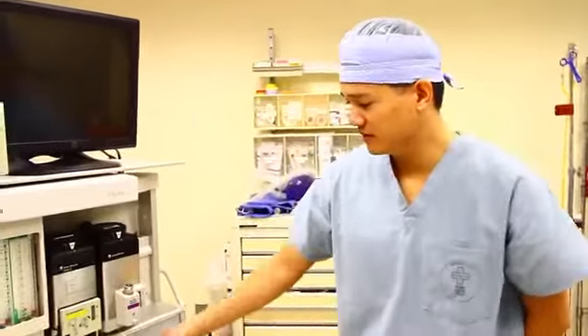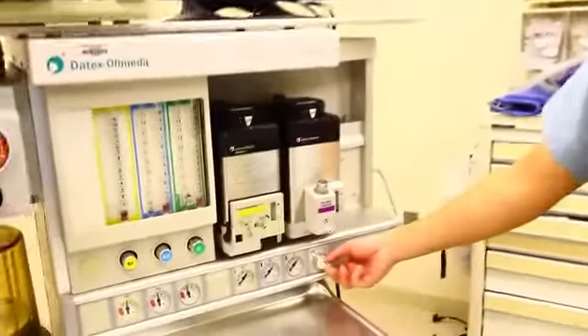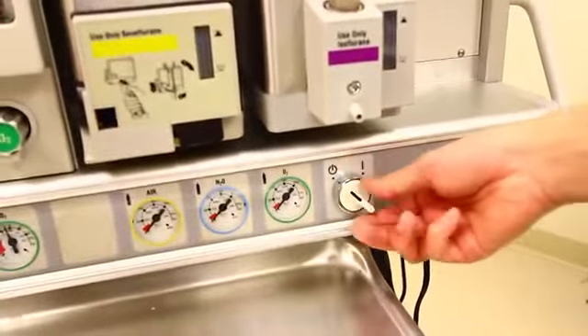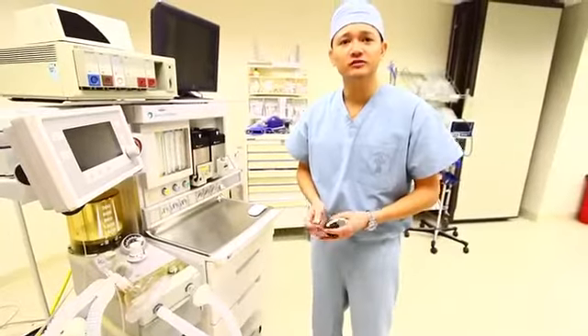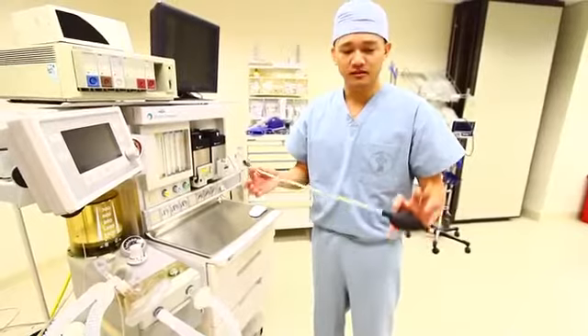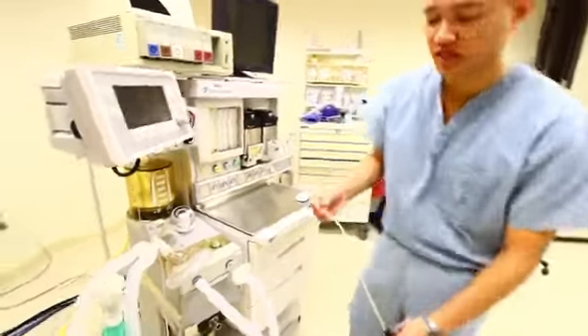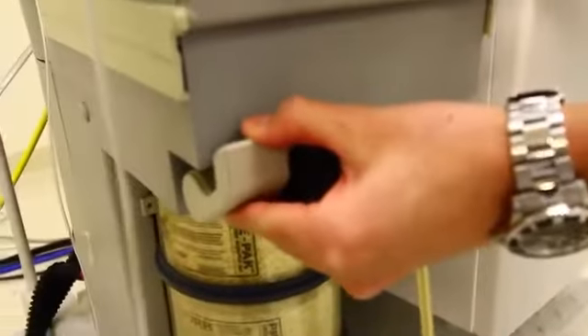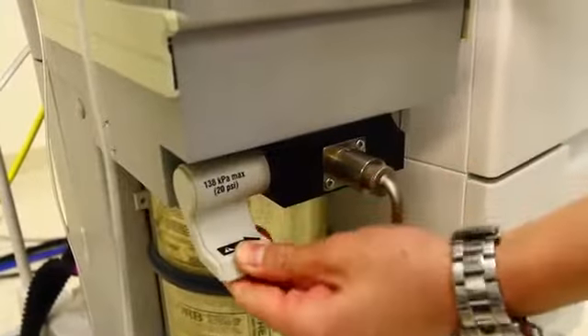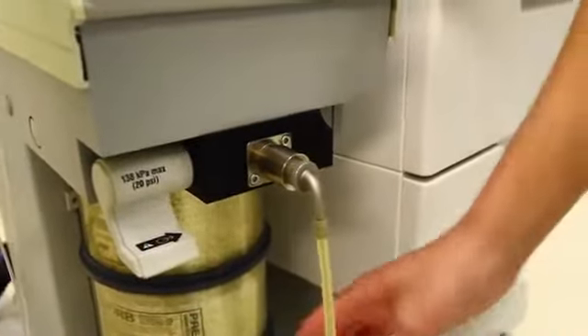Another part of the low pressure check is to ensure that the master switch is in the off position, which is denoted by the circle with the line. The next thing you want to do is to connect a suction bulb to the common fresh gas outlet and then flip the common fresh gas outlet switch. This opens the system.